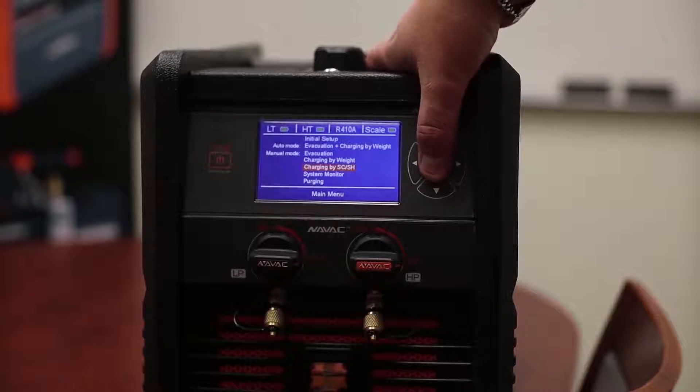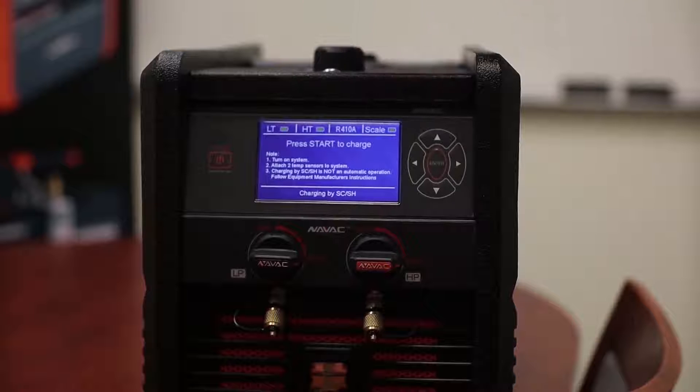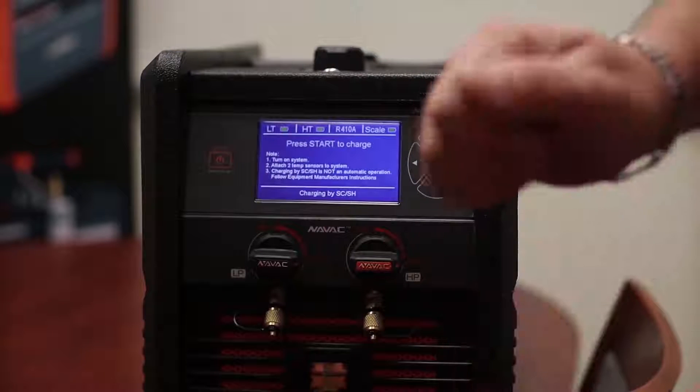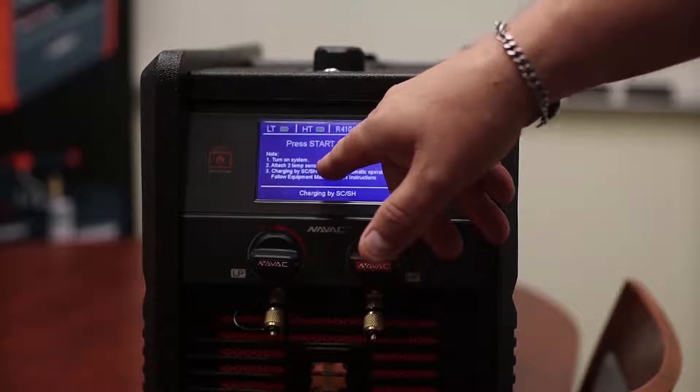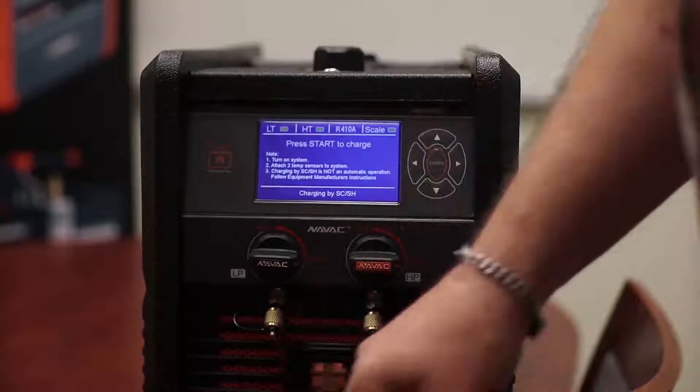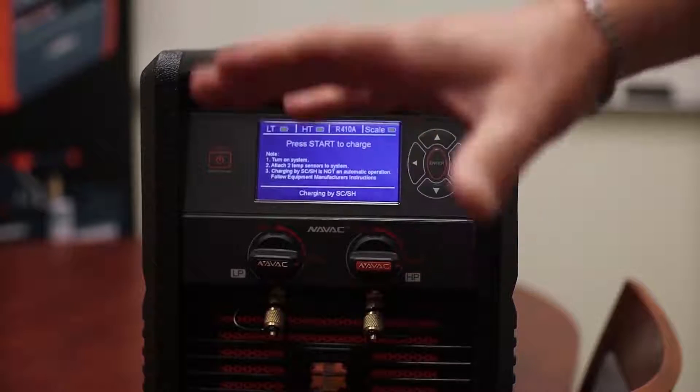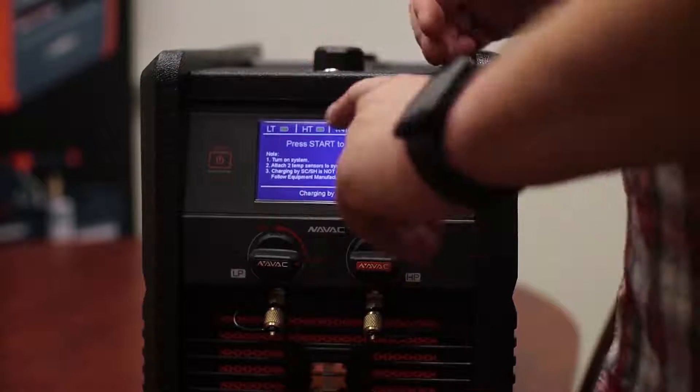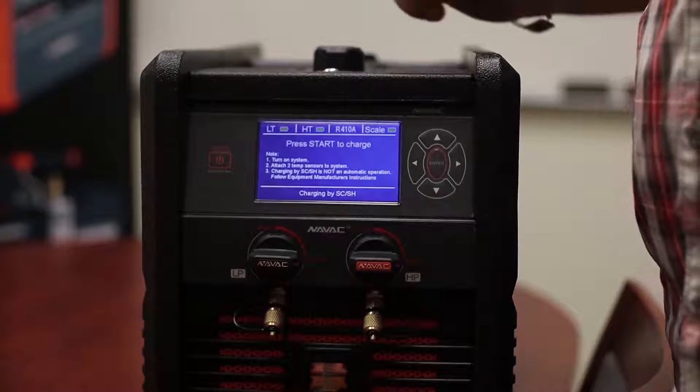Charging by superheat subcooling. So again, we've got everything connected. We've got our hoses, our tanks. It tells us, turn on the system, attach the two temperature sensors to systems. So we've got our high and low side. We attach them. Charging by superheat subcooling is not an automatic operation. We're not going to program our target subcooling and push start and let it do it. That's not the way it works.